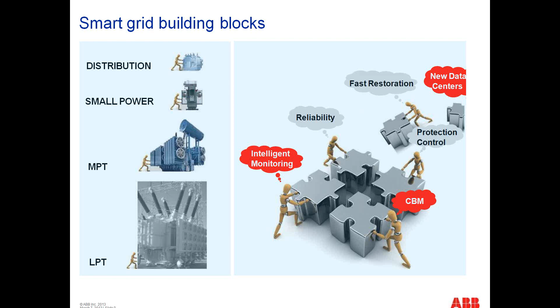In terms of the Transformer Assessor's Toolbox, in the old days you took an oil sample, cut the power to the transformer, and did a power factor and capacitance test on the main transformer and the windings. You really didn't want to get too intrusive on your transformer. In fact, statistics show that if you mess with the transformer, there's a chance you're going to mess it up, so you don't want to touch it unless you're going to do something positive for it.